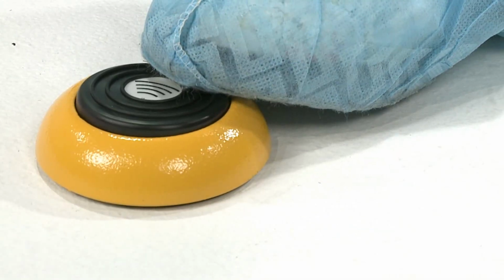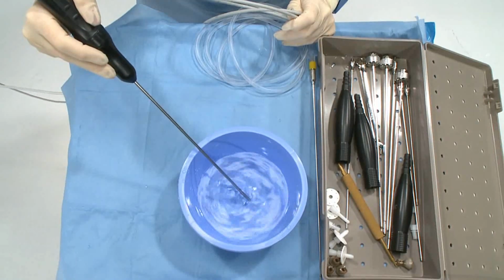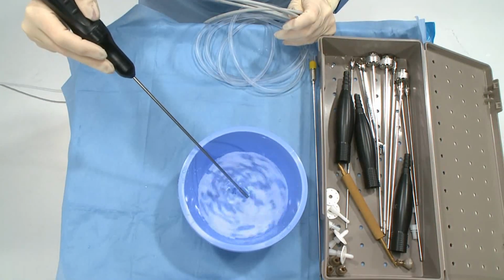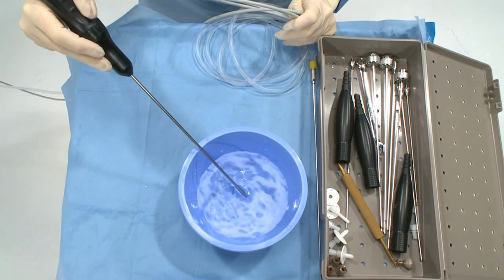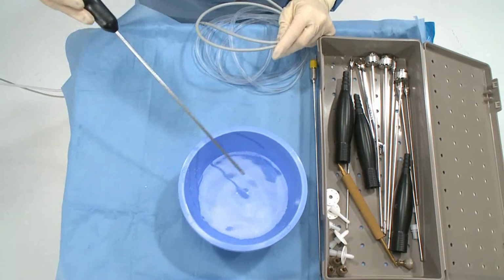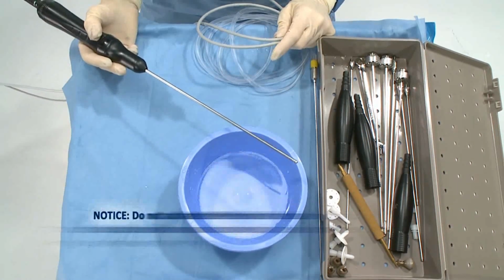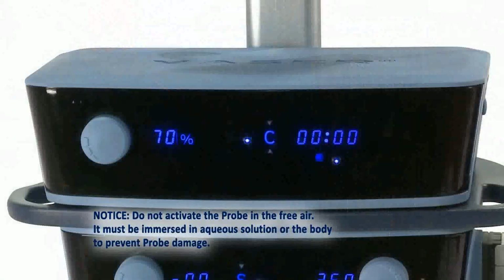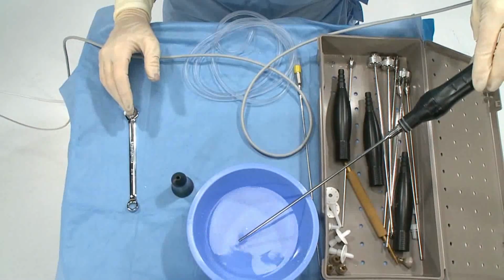Depress the Vaser foot switch. If the handpiece is working properly, you should hear a high-pitched sound and see bubbling in the water. You should not see or hear any fault warnings. If the bubbling is weak or non-existent, check that the amplitude is at 70 to 80%. If the system faults or doesn't do anything, the Vaser handpiece may be damaged.